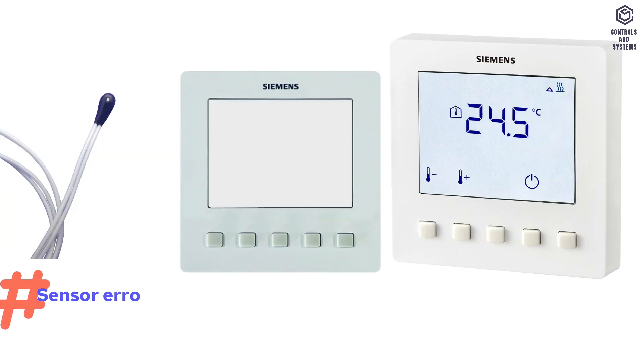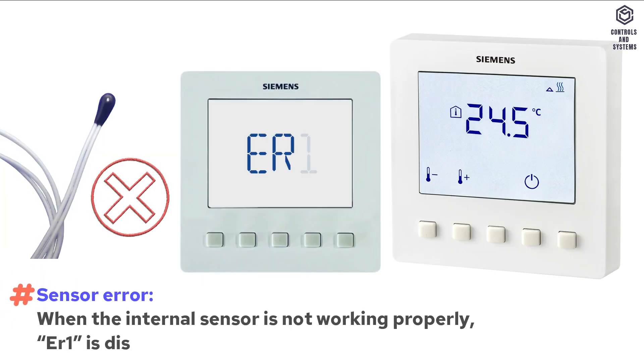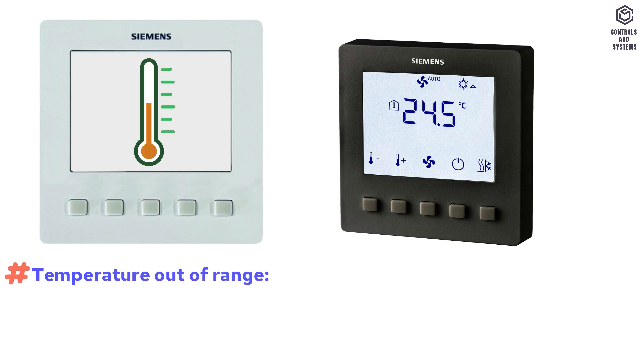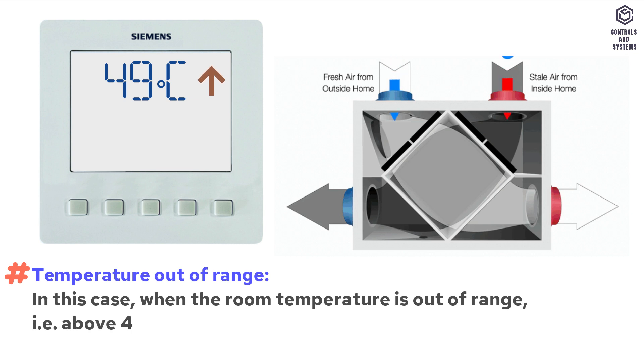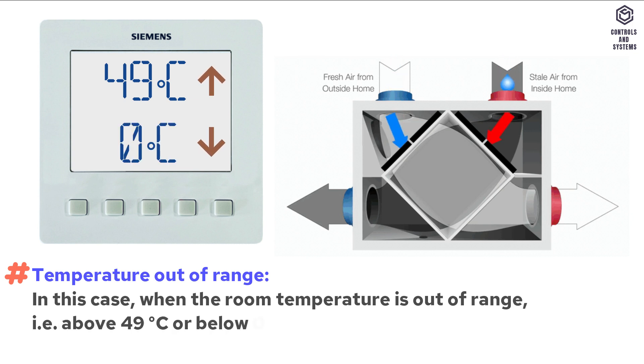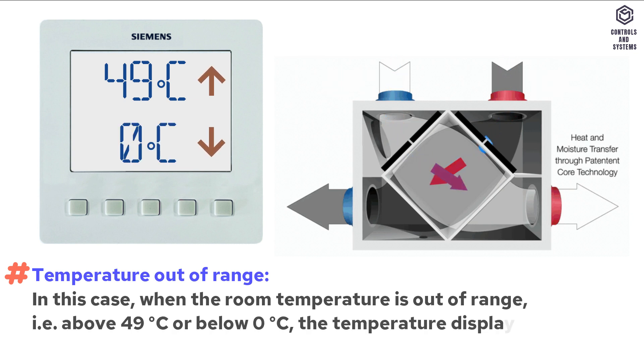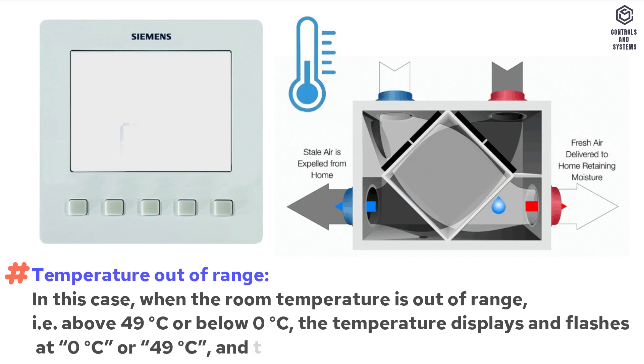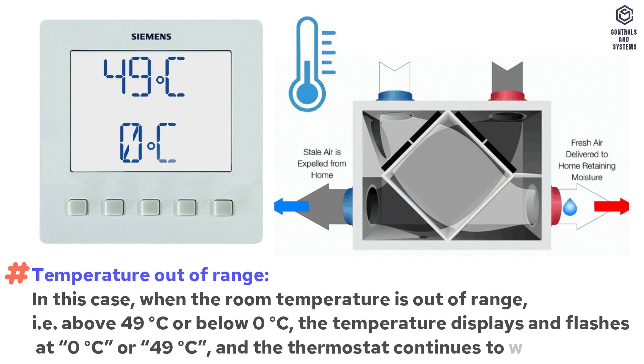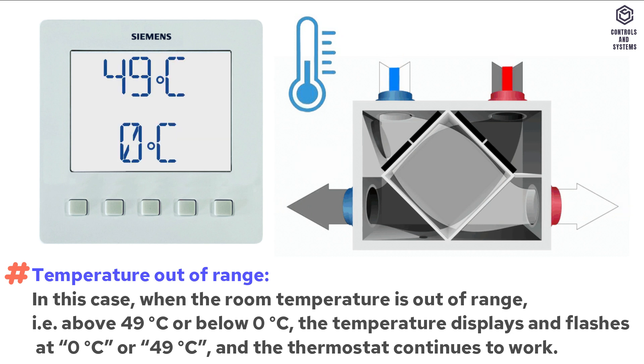Sensor error: when the internal sensor is not working properly, ERR1 is displayed. When the room temperature is out of range — that is, above 49 degrees Celsius or below 0 degrees Celsius — the temperature display flashes at 0 degrees Celsius or 49 degrees Celsius, and the thermostat continues to work.